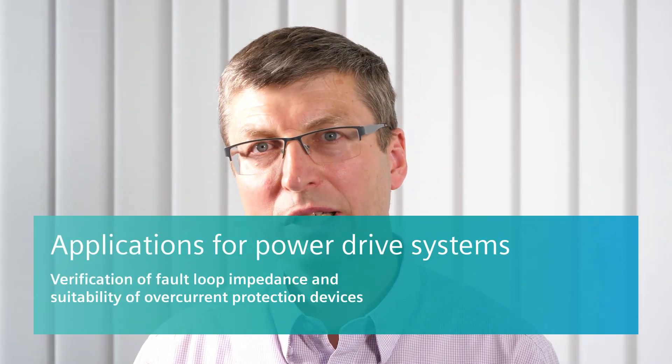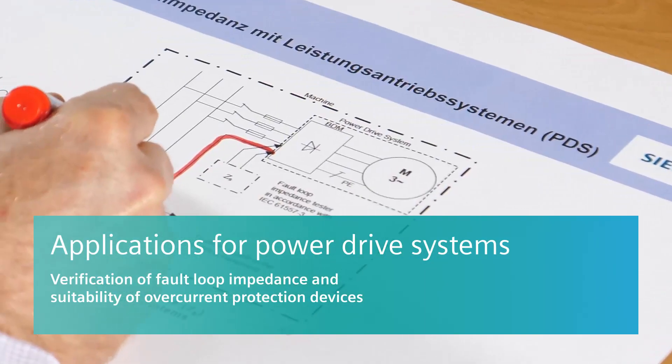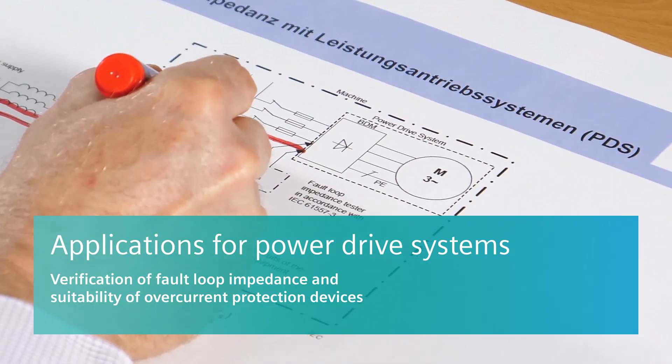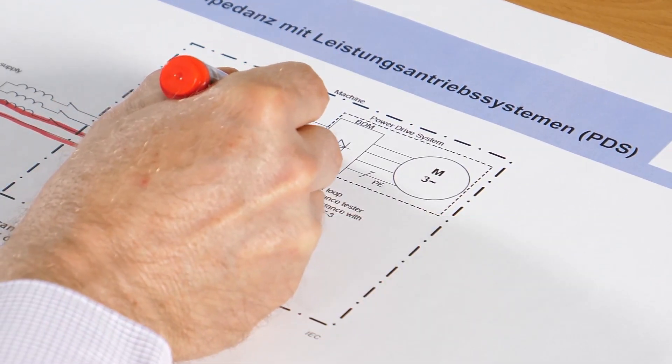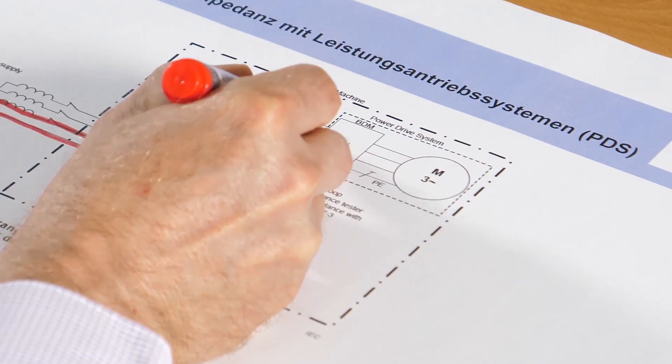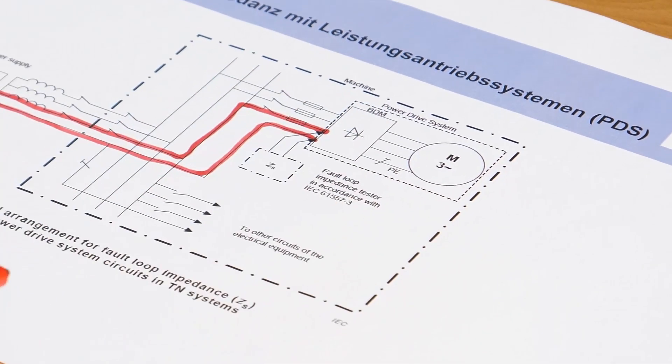Let us start with the applications for power drive systems. Here a fault loop measurement has been newly incorporated into the standard, which automatically switches off to provide protection. It precisely describes the tests and measurements that the user must perform in order to implement this protection in practice.